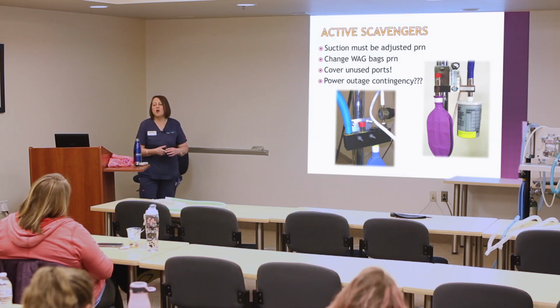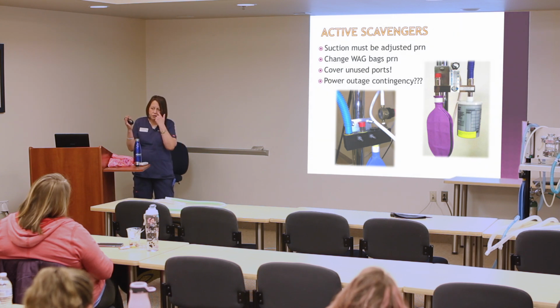And probably the most important thing I want to stress to you guys is maybe you have that 200-pound dog and you have a 5-liter bag on your machine. If you're going to give that animal a breath and you're going to try to empty that bag, then you actually have to watch this bag on the bottom of these machines to make sure that you're not overburdening the bag, because you have to wait for the scavenger to do its job. So you might have to squeeze a little bit, watch your bag down bottom get big, and then slowly get small, squeeze a little bit more, wait for that bag to catch up.